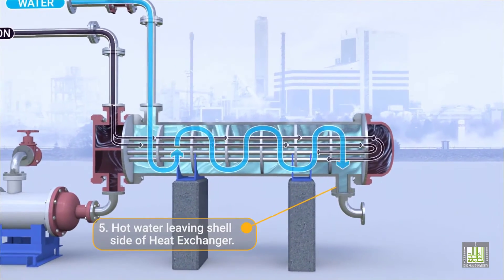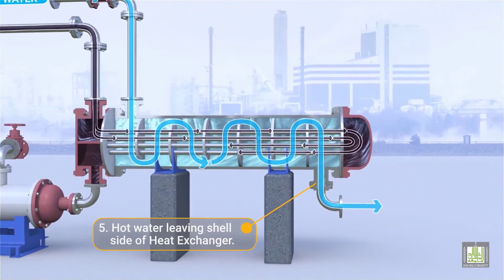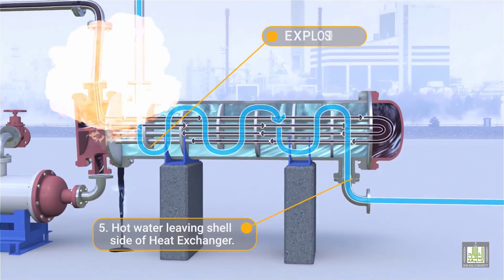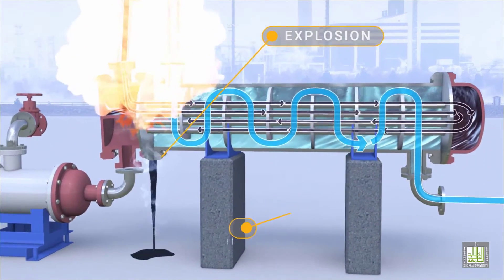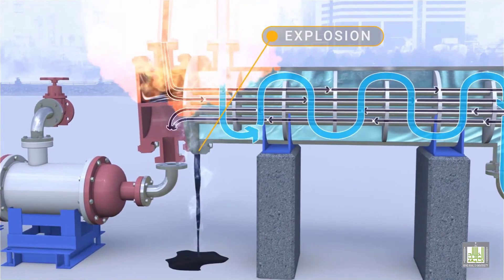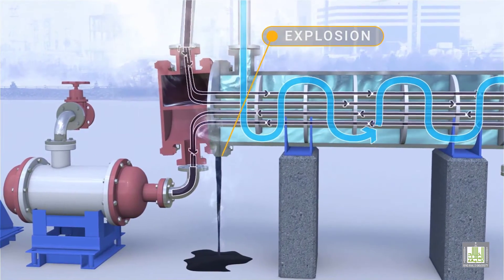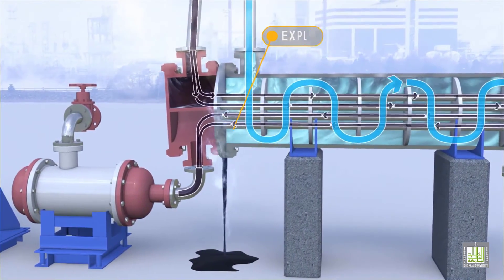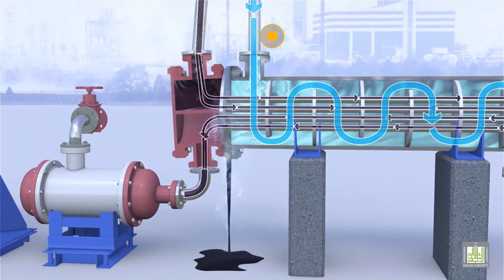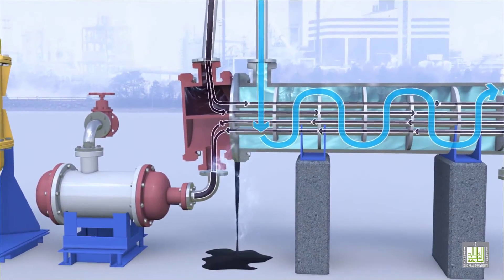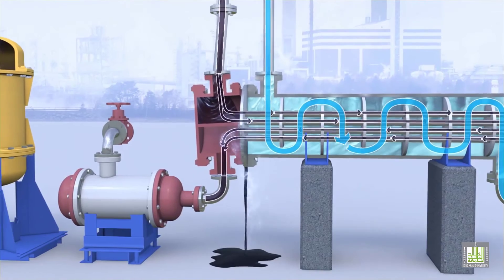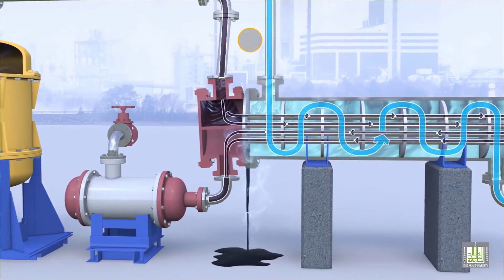5. Hot water leaving the shell side of the heat exchanger. The heat exchanger is typically provided with low or high point vents to remove water from the tubes or the shell. Uncontrolled mixing of water with hydrocarbons can generate high pressure conditions and can damage systems that are not equipped with pressure relief devices.